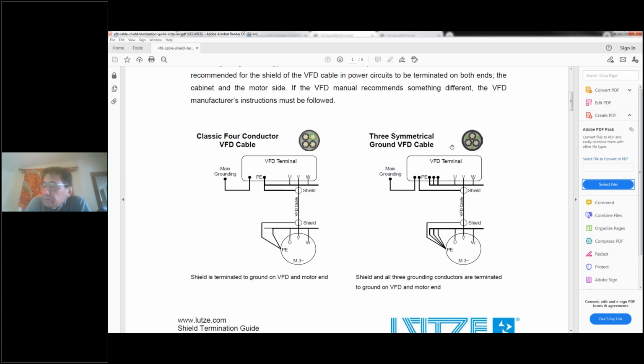Craig and I had that pleasure of being together under the gun, and I think we collectively spent probably 40 hours or so, not to mention the electrical engineer and the electrical contractor, all the vendors that had to contribute. We finally got the problem solved, but we would have been much better off if we had used a better cable at installation. So, again, reviewing, we addressed the thermal issues with an innovative approach to installing VFDs, eliminating air conditioners. We're recommending that you use inverter duty cable.